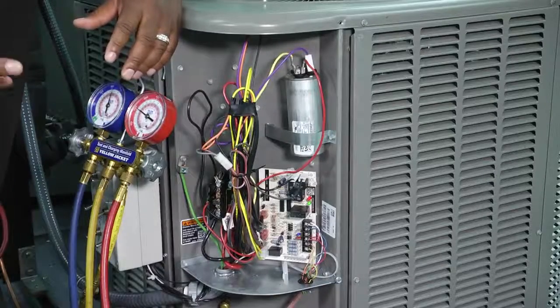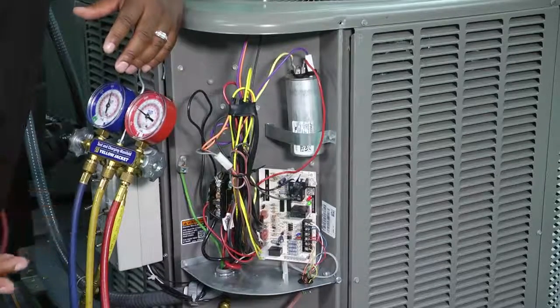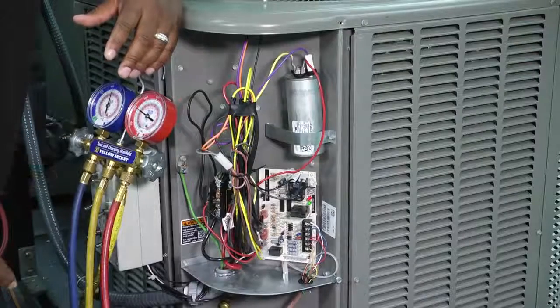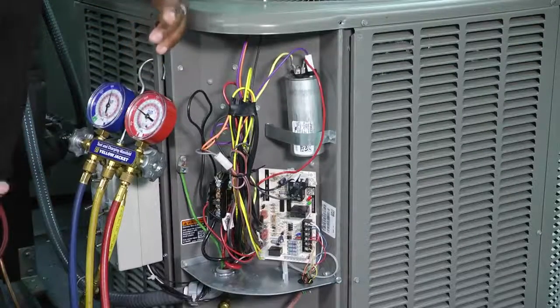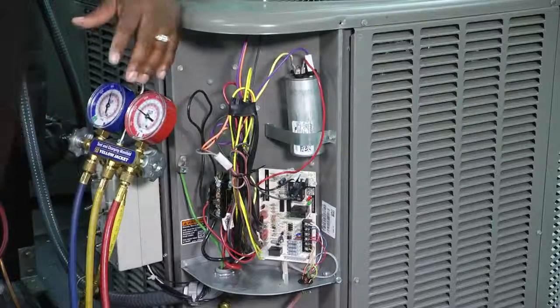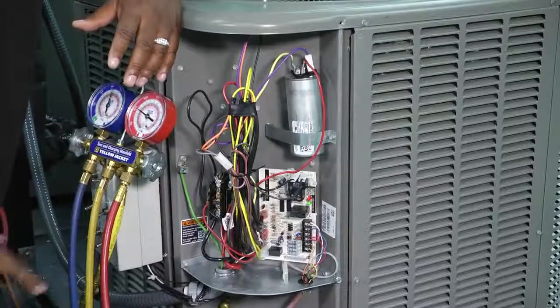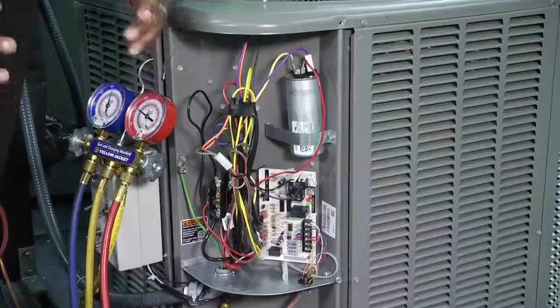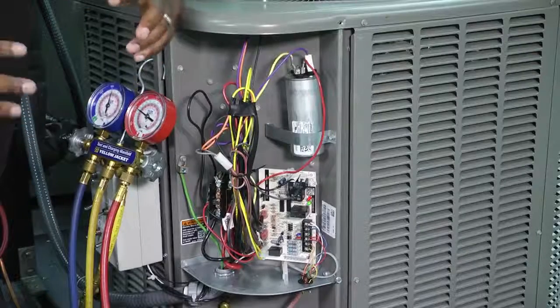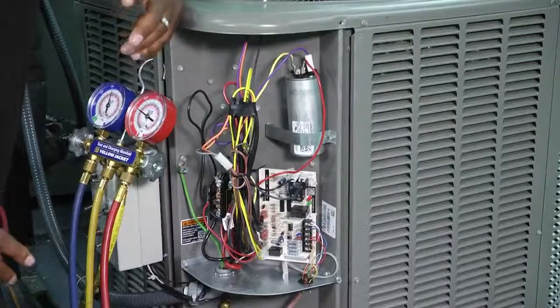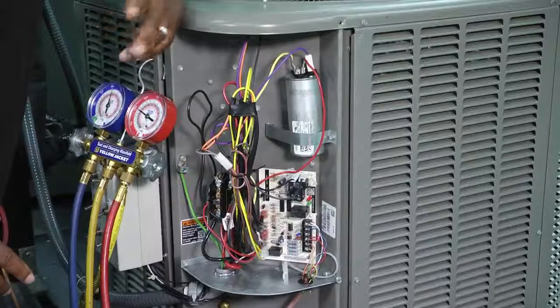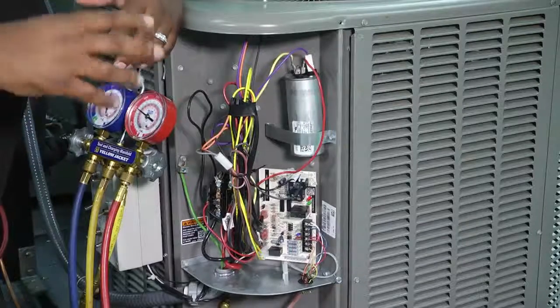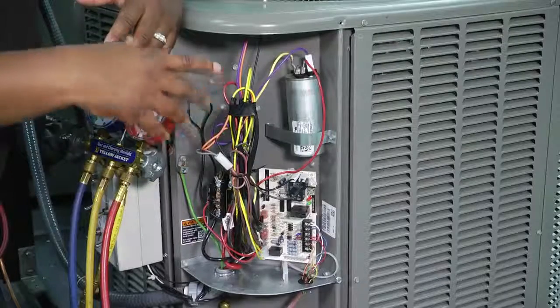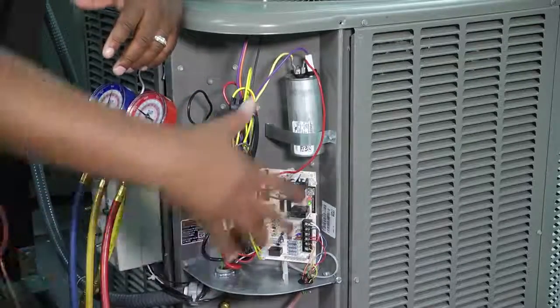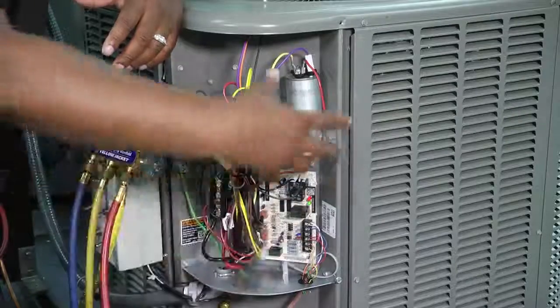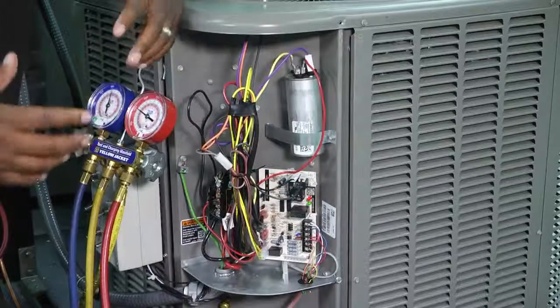Also, you have to educate the homeowner that the sprinkler that comes on is not the proper way to clean this coil. So just because they have a sprinkler system doesn't necessarily mean that their coil is getting clean. And another reason is we all, especially here in Texas, we all want to have these nice, beautiful lawns that are maintained and mowed once a week, sometimes twice a week, sometimes every other week. And every time that happens, be it from ourselves and or our neighbors, we can find a situation where our coils have now gotten impacted with all of that dirt and debris.